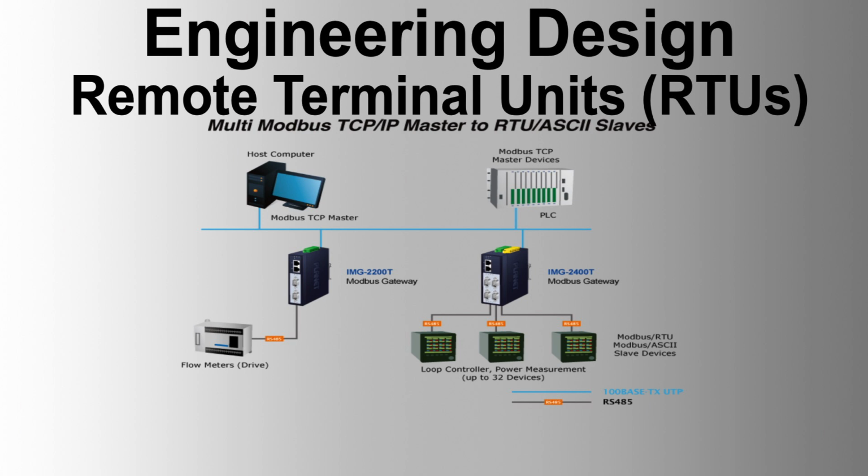I/O hardware specifications: RTU I/O hardware specifications include analog input modules with isolated inputs, high resolution, and accuracy. Analog output modules with isolated loop power and high accuracy. Digital input modules with wide-ranging inputs, high-speed counting, and SOE recording. Digital output modules with high contact ratings and external relay boards for higher-rated contacts.